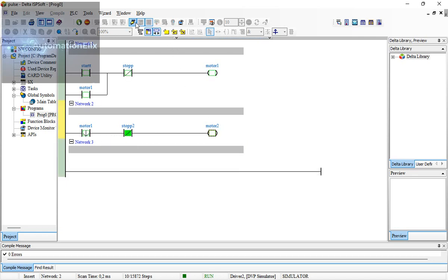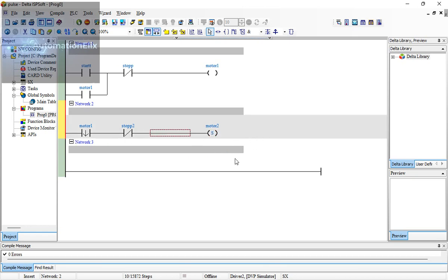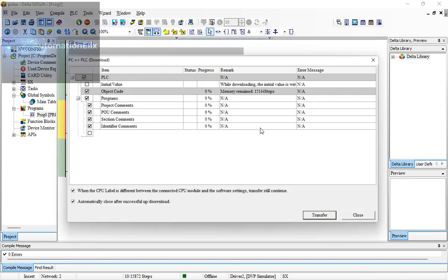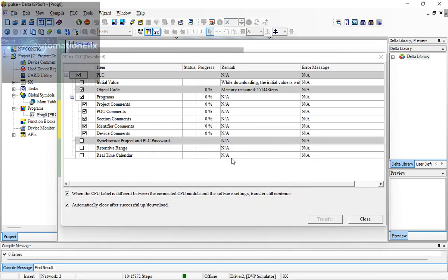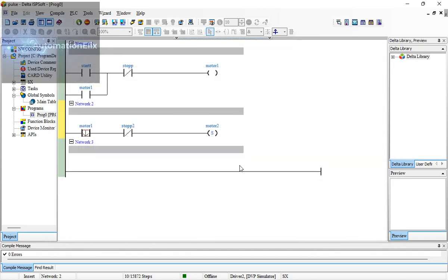If you change this into a set, you can actually catch that one scan time, because now it switches on and off, but you don't see it because it's only a pulse. So let me do it this way. I want you to see the difference. Now you're gonna actually see the set on, because a set can actually detect one pulse. There it becomes on. You don't switch it off until you reset it.